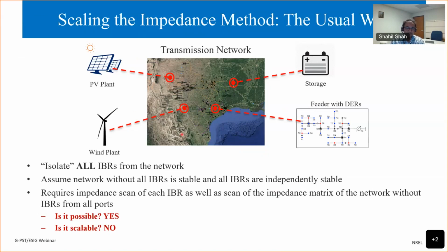And this usual approach, which is basically based on that standard impedance-based stability analysis, works fine in theory, but it's not practical, because here we need to scan the impedance of all the IBRs as well as of the network, looking from all the ports of the IBRs. So for example, here we are seeing 4 ports. So we need to know the impedance of the network from those 4 ports, which gives us a 4x4 matrix of impedance transfer functions.